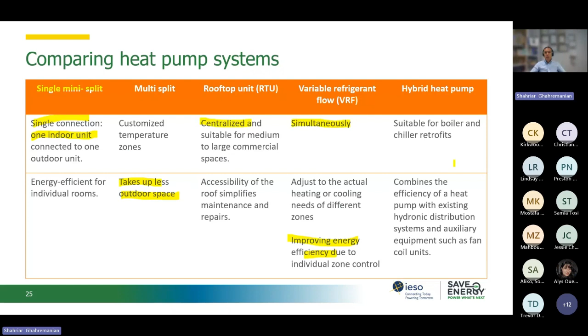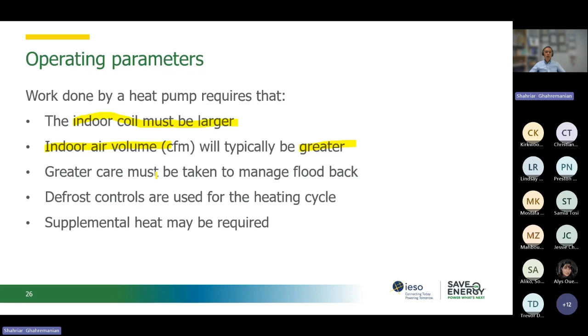There are some parameters that we also need to work on. When we switch from the existing system to the heat pump, typically the indoor coil needs to become larger because the heat pump is operating on a different system. On the same note, the indoor air volume, the amount of air that we need to supply, needs to become larger. For example, if we were providing 1000 CFM, now maybe we need to provide 1800 CFM. That's the difference because we are switching to a heat pump. Inside our building, we have an air movement or air distribution system. One thing that we need to consider is flood back. Flood back is when the refrigerant comes back to the compressor and can damage the compressor. So we need to be careful. But these days the technology is available from the manufacturers, and this doesn't happen so often.